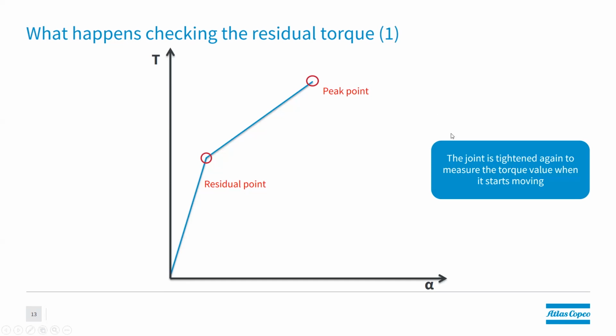So the section from the residual point, where the joint starts moving after we've won the static friction, up to the point where we stop applying torque, which is the peak point — what are we interested in? We're interested in the residual point, because that tells us what torque was left by production after the joint had been tightened.